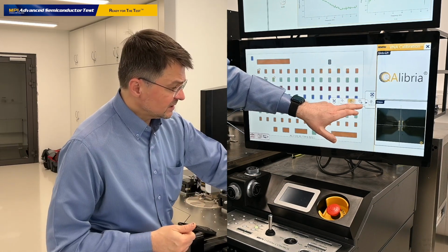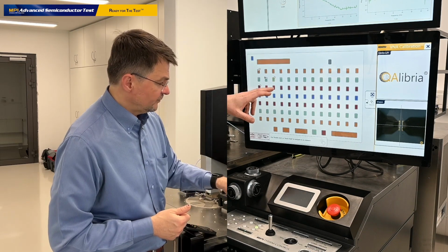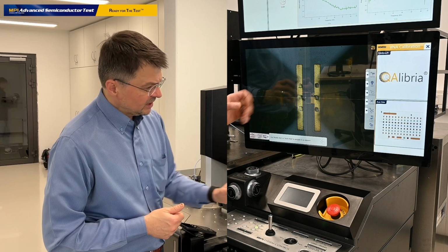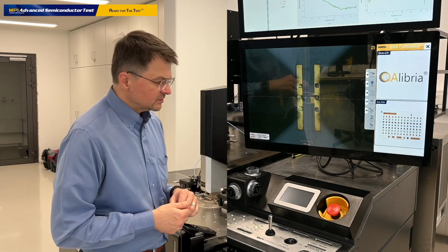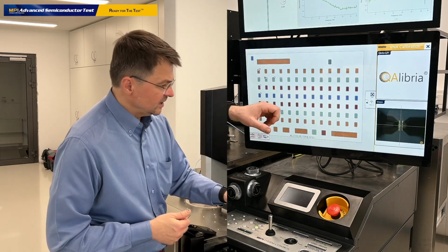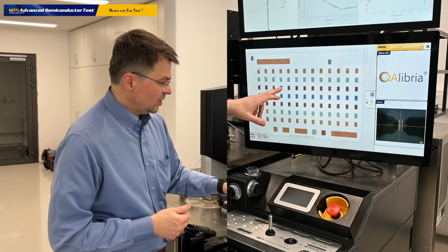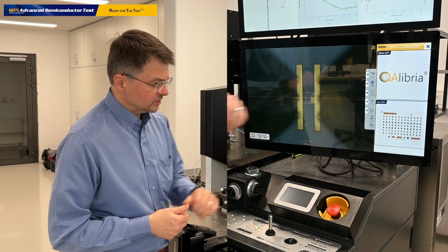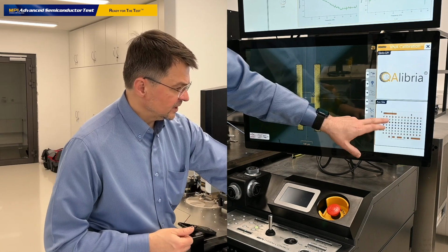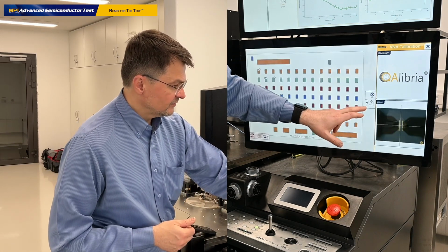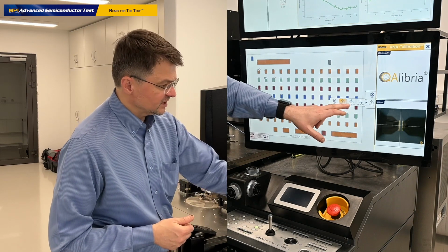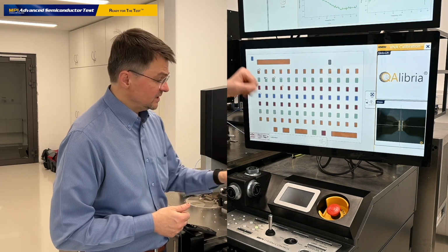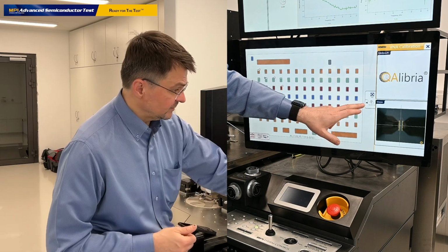So let me double check the quality of, say, a short standard from the same column. It looks like the short had several touches already. It was heavily used. How about the next one from the line? Oh, this is a very good short. I actually like it. So that's why let us use it for the calibration process. We are currently over this element, used for the cal. Now we selected this calibration standard for the calibration process.